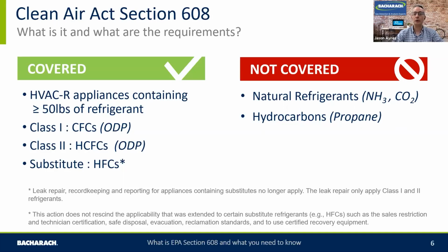Historically, it was around ozone depletion refrigerants, so that was aligning with the Montreal Protocol. So you'll hear the terminology class 1 and class 2. They're in essence CFCs and HCFCs. So if you've got appliances that are greater than 50 pounds with a CFC or HCFC refrigerant, it falls under 608. What's also been added to 608 in terms of capturing the information is HFCs as well, or what we term the substitute refrigerants. So they are the equipment that you need to be aware of within your organizations. If you do have those types of assets and equipment, you need to be aware of that, and there's some reporting requirements under EPA.